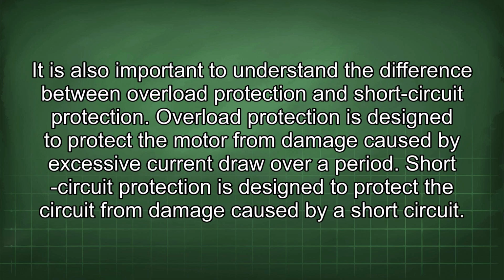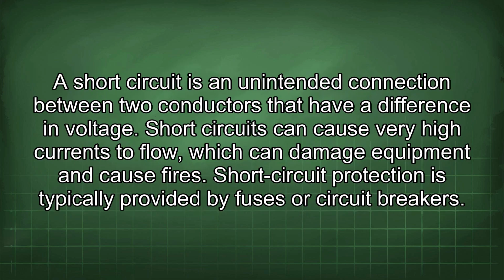It is also important to understand the difference between overload protection and short-circuit protection. Overload protection is designed to protect the motor from damage caused by excessive current draw over a period. Short-circuit protection is designed to protect the circuit from damage caused by a short circuit. A short circuit is an unintended connection between two conductors that have a difference in voltage. Short circuits can cause very high currents to flow, which can damage equipment and cause fires.